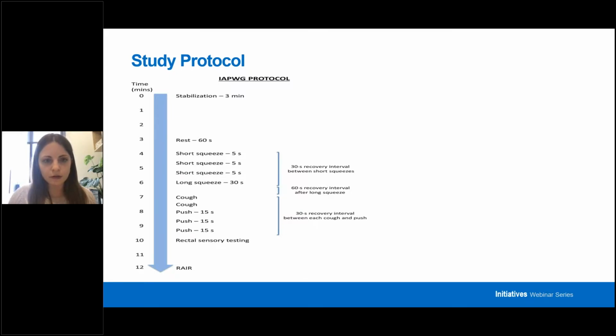So as the performer of the test, you increase the air by 10 cc's each time, using the 3-way stopcock to make sure that air is staying in the balloon and not coming back out. You usually wait 30 seconds between each inflation. The maximum air you're going to put in these balloons is about 320 mL.